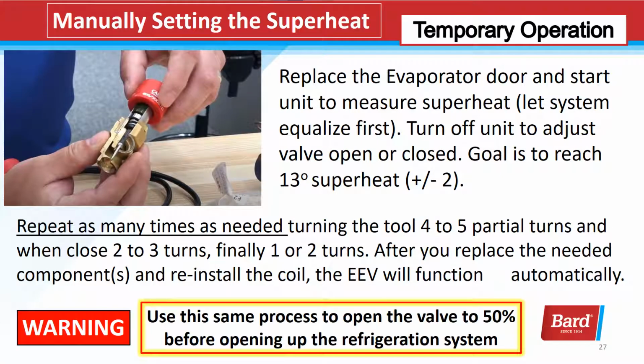Replace the evaporator door and start the unit to check superheat. Let it equalize for a few minutes and determine if you need to open or close to increase or decrease the superheat. Remember, the directional arrows for open and close are on the top of the EEV tool. Repeat as many times as needed, turning the tool 4 or 5 turns in the beginning. When you see you're getting close, drop that down to 2 or 3 turns, and finally, when you get zeroed in there, you might only be doing 1 or 2 turns on your last trip inside the evaporator compartment.